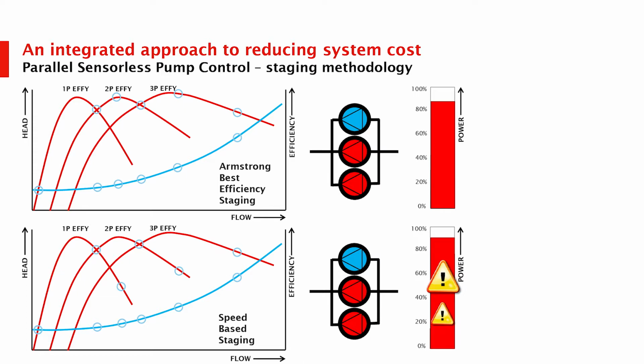Same thing will happen on the right: the power of the 3 pumps will be much less than the power of the 2 pumps. Ultimately, if you run everything flat out, there's no savings. When you get 3 pumps running, whether with traditional staging or a more contemporary approach, there's no savings if the building really is at full load. But we also know, generally, and certainly according to ASHRAE, that 90% of the time buildings run at less than 60% load.